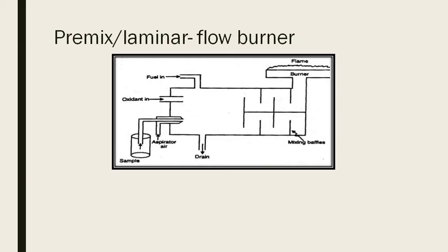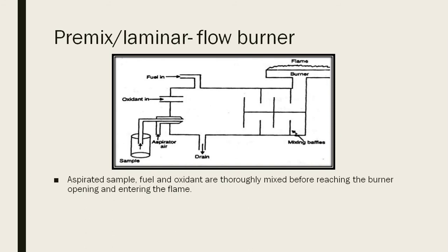Next burner is the premix or laminar flow burner. As shown in the diagram, this burner uses mixing baffles, and you can see that there is a longer path length for the sample to reach the flame. Here the aspirated sample, fuel and oxidant are thoroughly mixed before reaching the burner opening and entering the flame. Gases move in a non-turbulent fashion, that is in a laminar pattern, hence the name laminar flow burner.